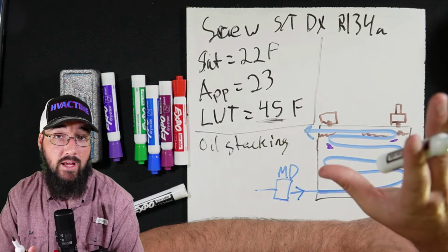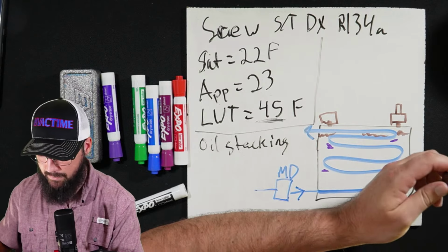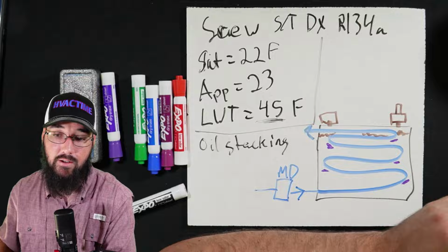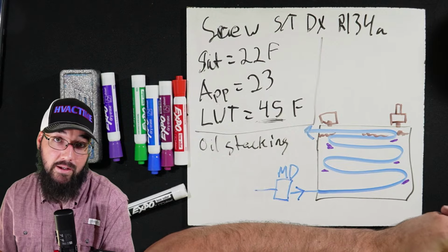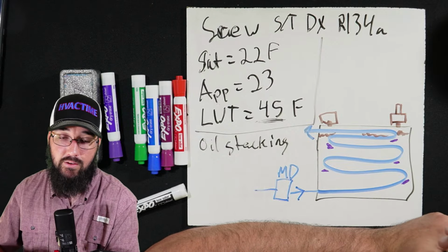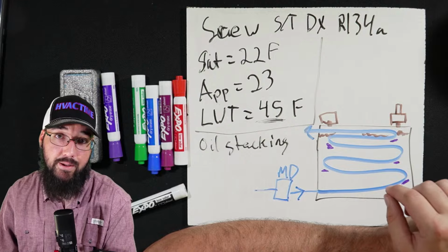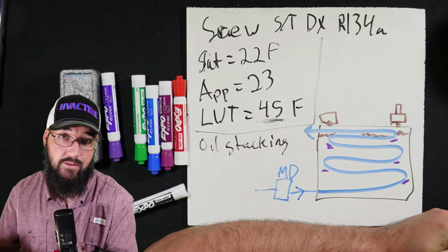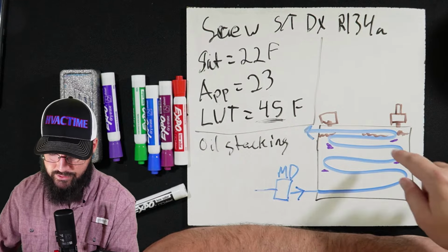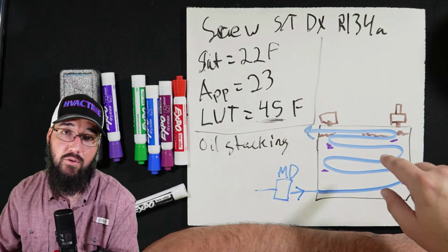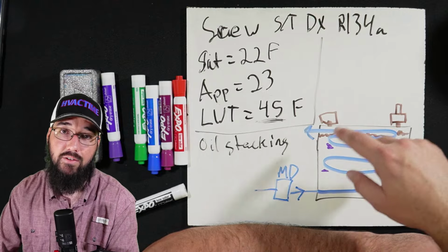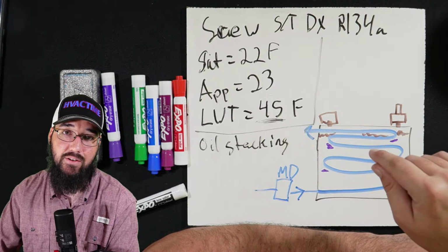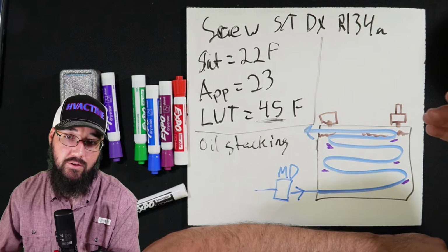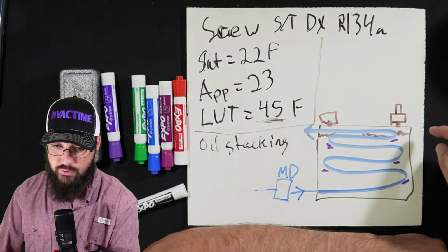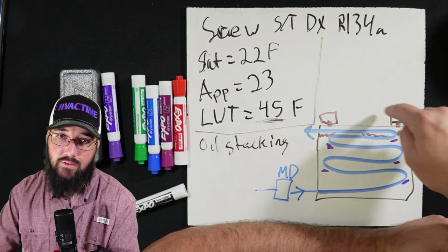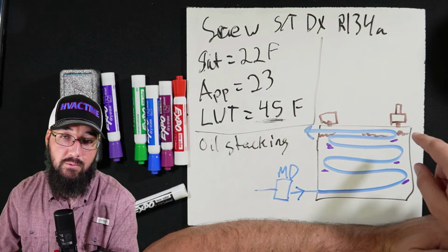And even though you'll have good DP, I've had this happen. It's the craziest stuff, and it can be a pain to troubleshoot the first time you see this. You'll have perfect DP on your evaporator. It'll look great. But you're not actually making full contact with all the water in the circuit because the air has gotten trapped in there. And that is causing a higher approach with low suction pressures as an issue. So you'd be shocked how often this is a problem.